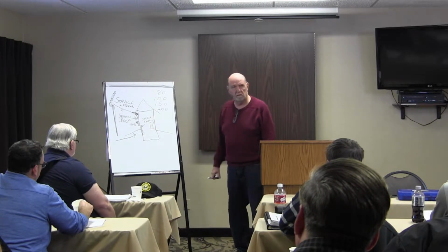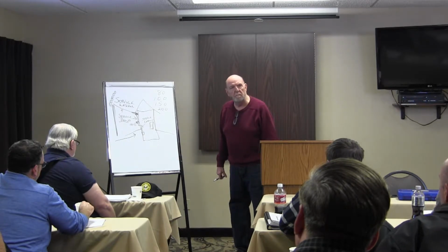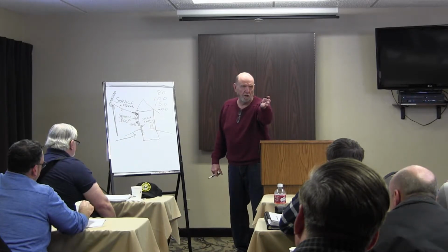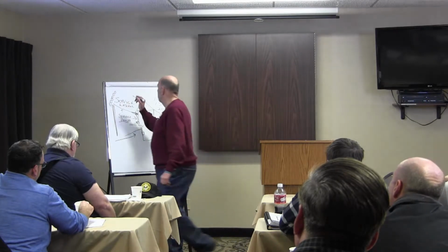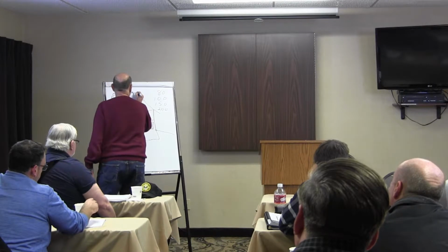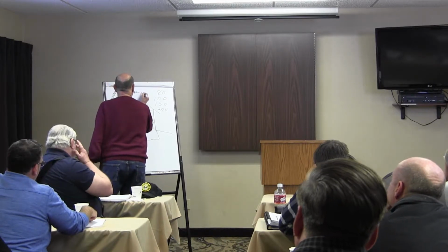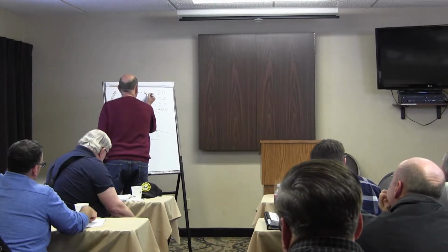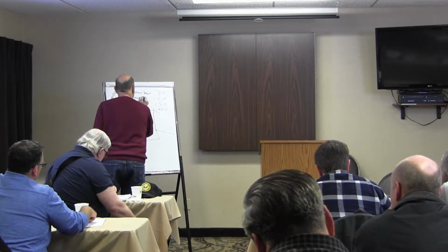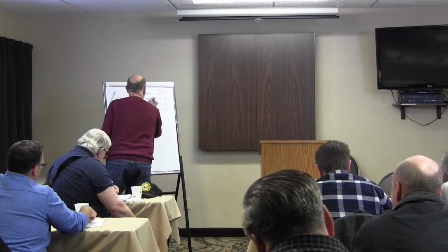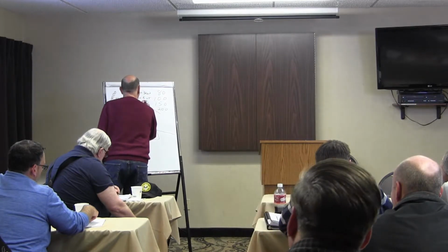The service entrance. We have to measure that. The meter has nothing to do with it. That's the only part you're wrong. The three things that you have to look at are the service drop, the size and rating of that wire, the service entrance, and then the main breaker.